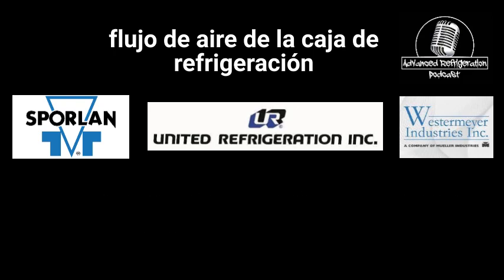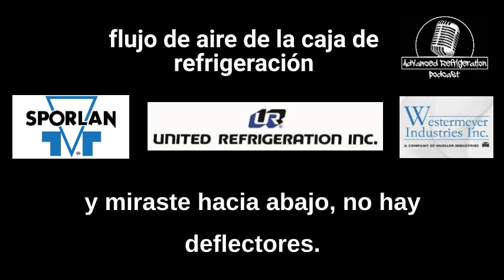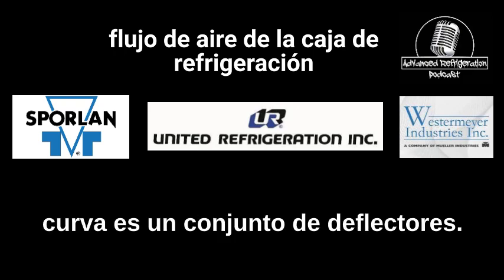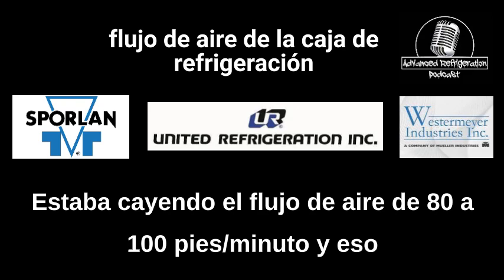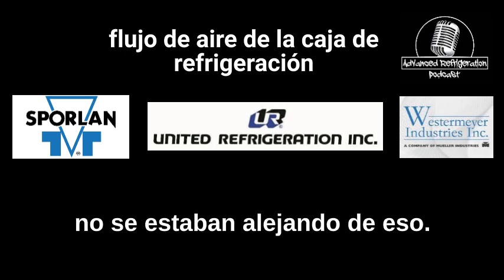Sorry. Yeah, so if you pulled the back wall down and you look down, there's no baffles. If you looked up, right before the curve is a set of baffles, and that's what was in there, and that's what was causing it. I mean, they were plugged solid. It was dropping the airflow 80 to 100 feet per minute, and that was enough where it was allowing warm air to come in and ice these cases up because the customer had such a stringent defrost spec, and they were rigid on it. They weren't moving off of it.